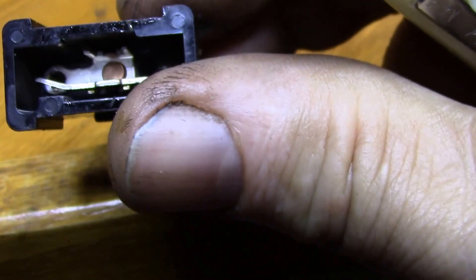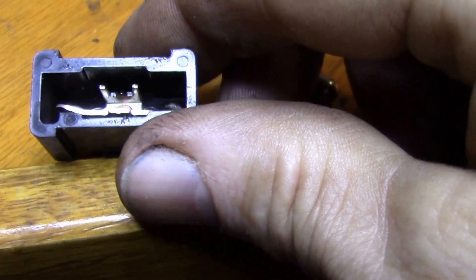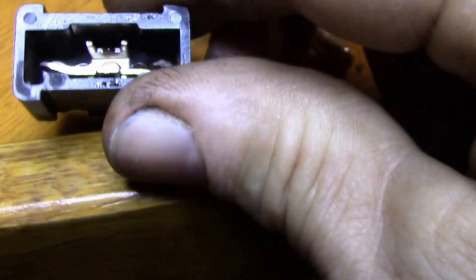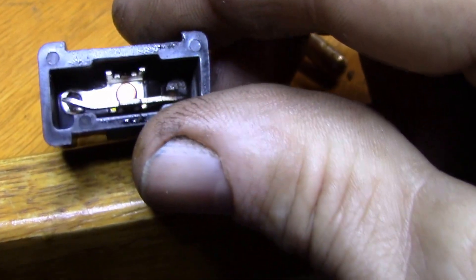I had to pop it apart. No real sign of corrosion, it just basically burned up the contacts. There's a little bit of shine you can see right in there. I could wipe off a little bit of some sort of liquid. I don't know if that's some of the oil from the coolant or what.